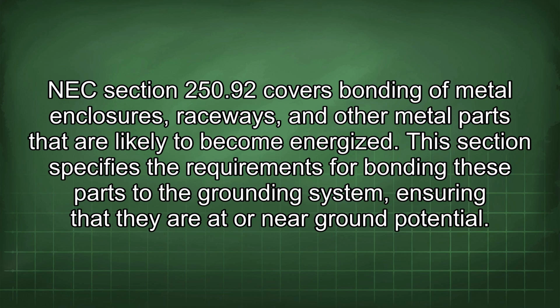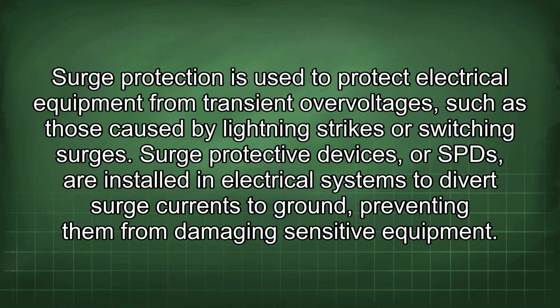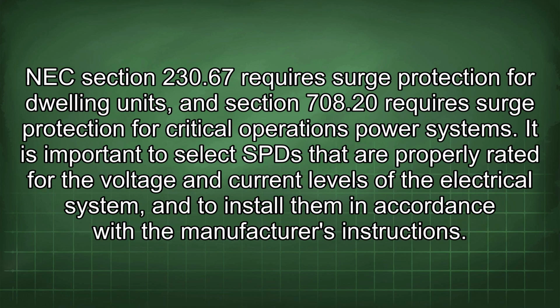ground potential. Surge protection is used to protect electrical equipment from transient overvoltages, such as those caused by lightning strikes or switching surges. Surge protective devices, or SPDs, are installed in electrical systems to divert surge currents to ground, preventing them from damaging sensitive equipment. NEC Section 230.67 requires surge protection for dwelling units, and Section 708.20 requires surge protection for critical operations power systems.